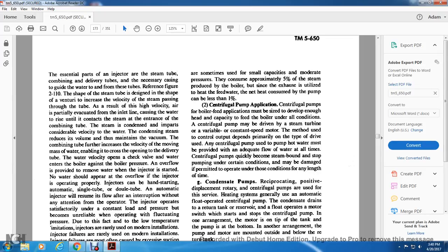Alright, centrifugal pump application. Centrifugal pump boiler feed applications must be sized to develop enough head and capacity to feed the boiler under all conditions. Centrifugal pumps must be driven by a steam turbine or a variable or constant speed motor. The method used to control the output depends primarily on the type of drive used. A centrifugal pump used with hot water must be provided with an adequate flow of water at all times. A centrifugal pump can quickly become steam bound and stop.